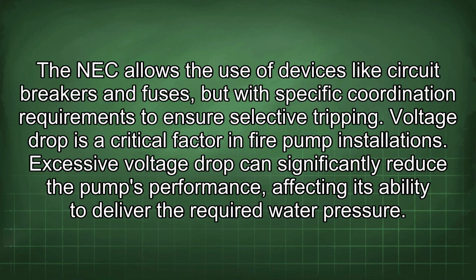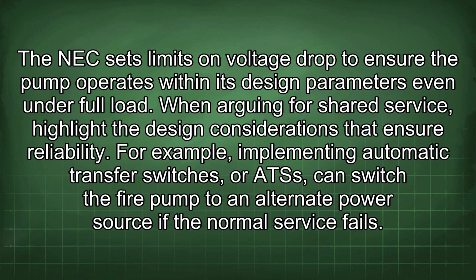The NEC allows the use of devices like circuit breakers and fuses, but with specific coordination requirements to ensure selective tripping. Voltage drop is a critical factor in fire pump installations. Excessive voltage drop can significantly reduce the pump's performance, affecting its ability to deliver the required water pressure. The NEC sets limits on voltage drop to ensure the pump operates within its design parameters even under full load.